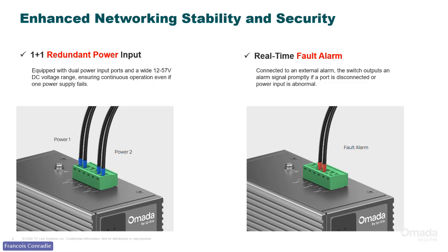As mentioned, we do have a redundant power input, so you can run two inputs into the device. The only thing is, if we're running the switch at 12 volts, you won't get the full PoE functionality or full PoE budget. You'll get a set budget whether you're using 12 volt, 24 volt, or 48 volt. But you can run the power in redundancy - you could have solar as the backup and battery as the main, or run two DIN rail power supplies in case one stops working.